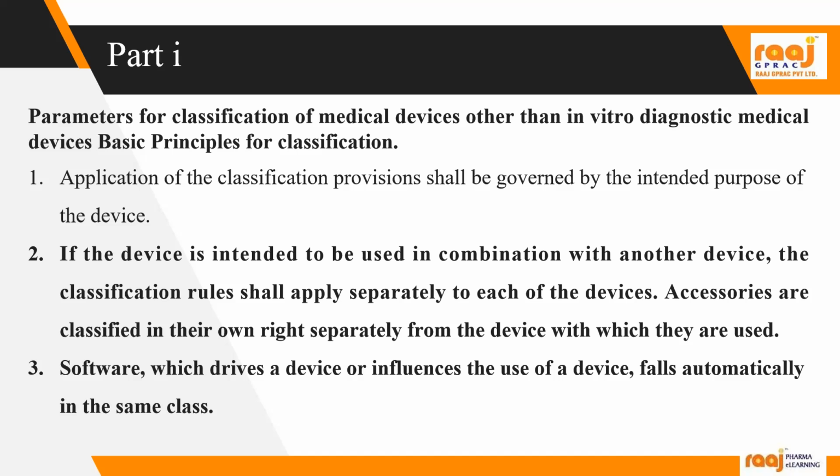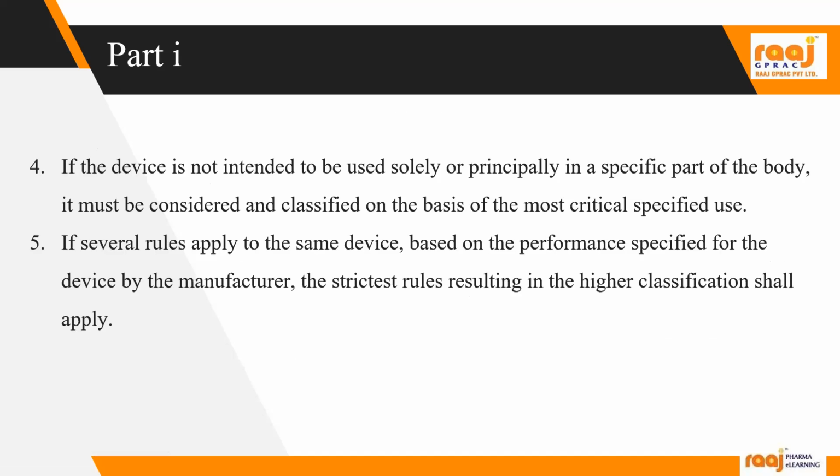Then sometimes software, like you have seen in the ECG machine or the automatic blood pressure machine. Software which drives a device or influences the use of a device falls automatically in the same class. Okay. Yeah.